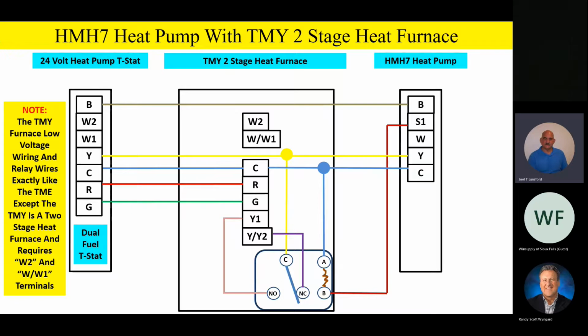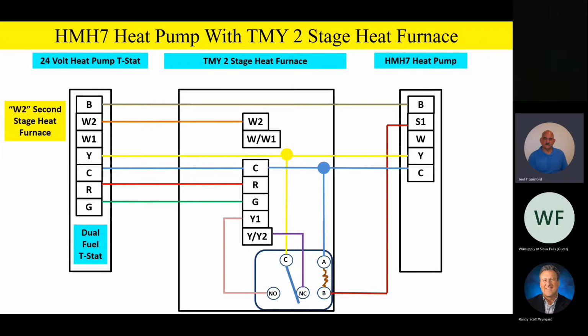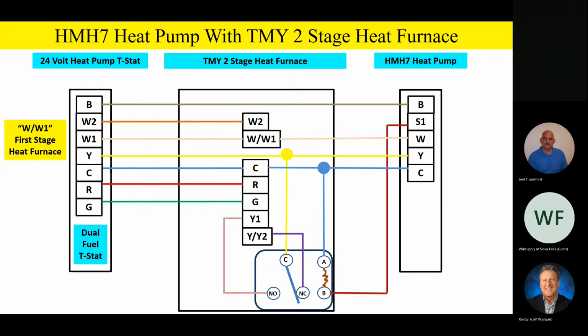So we're going to go ahead and take W2 from the thermostat over to W2 on the furnace, and then W1 from the thermostat to W/W1 on the furnace, and then W outside. So any questions or comments on how we're wiring up the single-stage TME and the two-stage TMY furnace before we do a little animation and show you how it's going to switch airflow like we did before? Any questions or comments? No, we're still good, Joel.